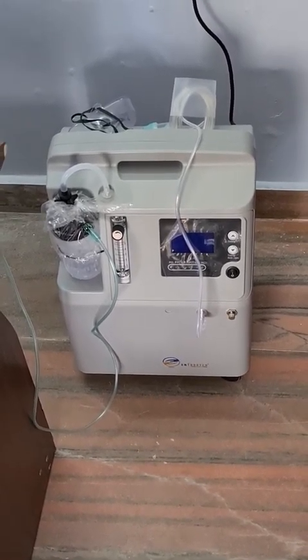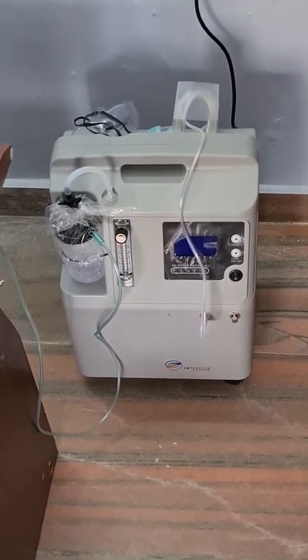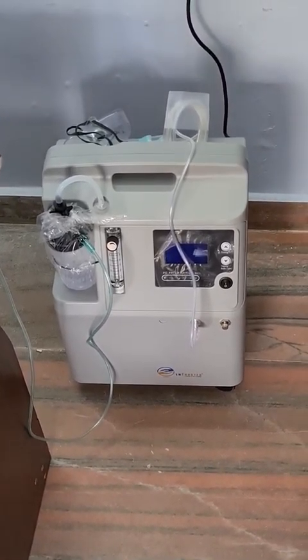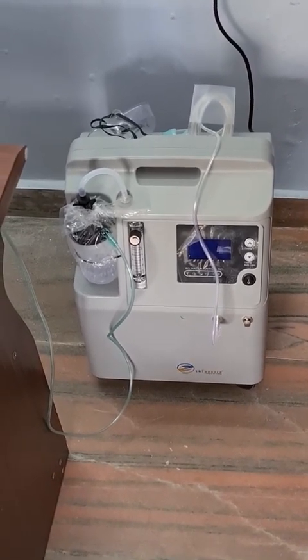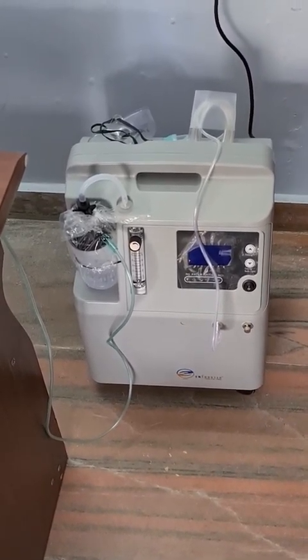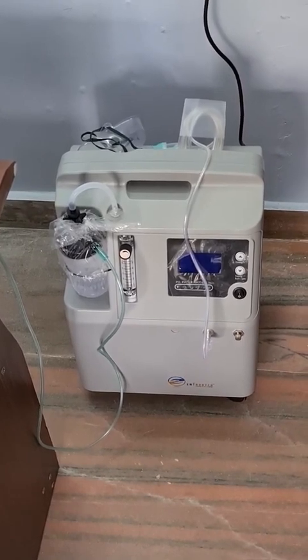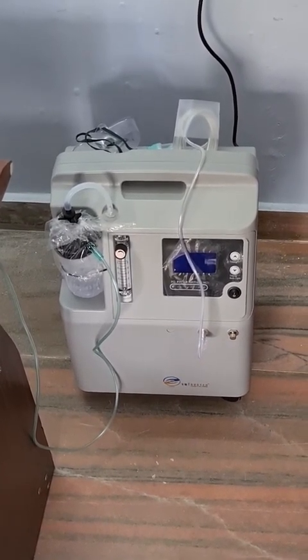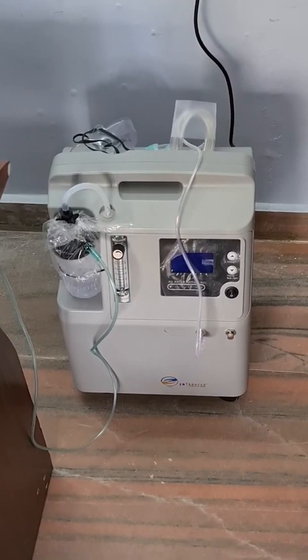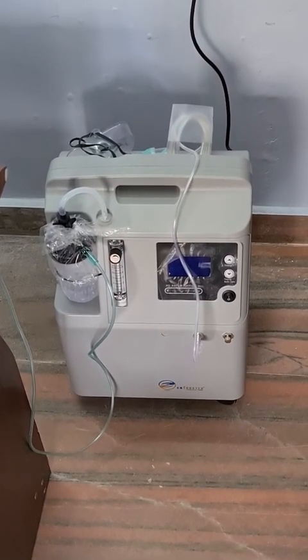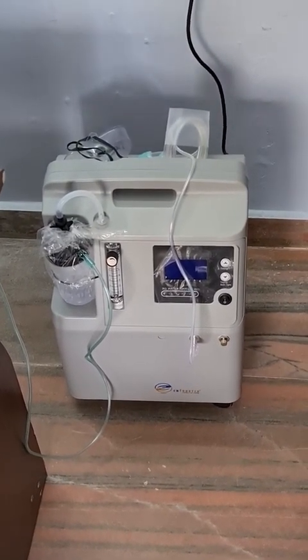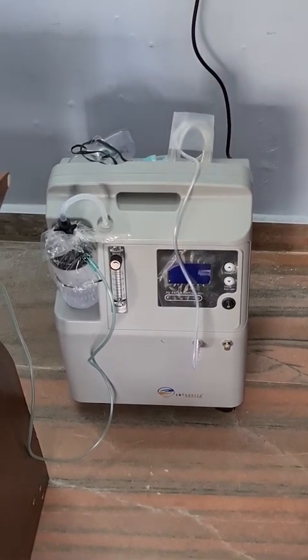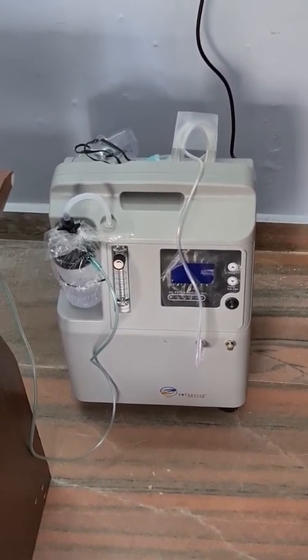And the question you may ask me: why is the machine only 350 watts but you require a stabilizer of 1.5 kVA? The answer is very simple. It is not like a TV or fridge. It has a compressor running inside, so the starting current will always be 5 times more. So it is better, and compulsory, to have a 1.5 kVA stabilizer. And that 1.5 kVA stabilizer should also have a maximum output voltage range of 230 volts.